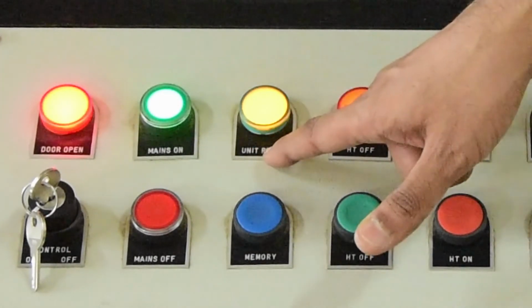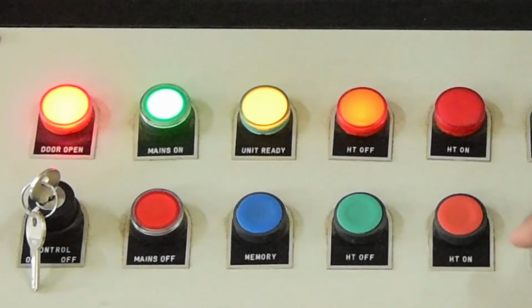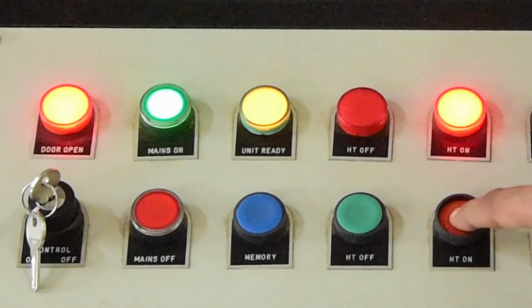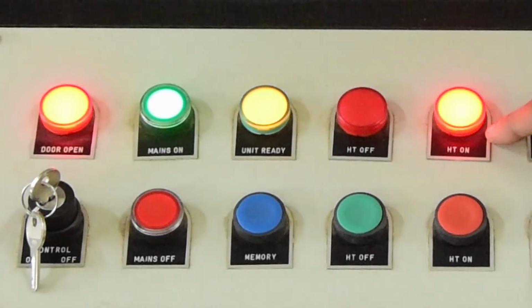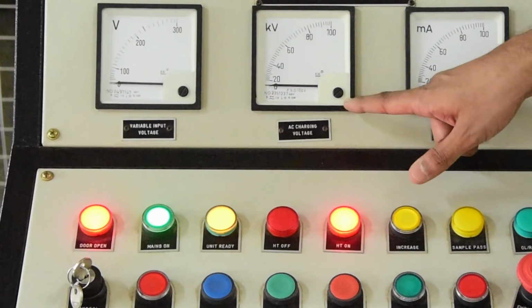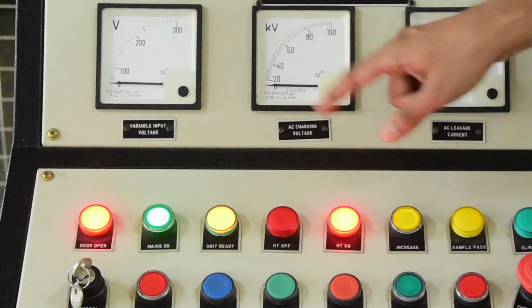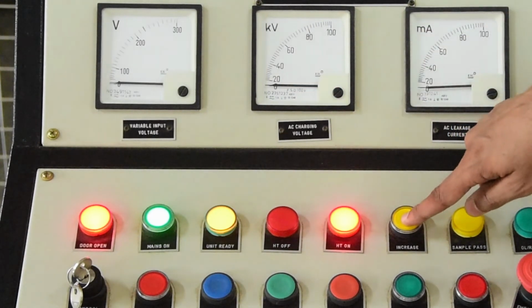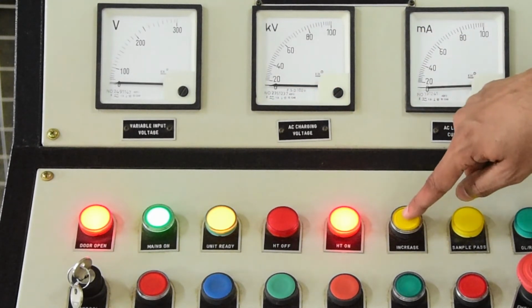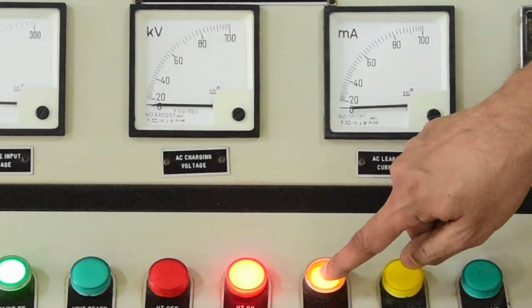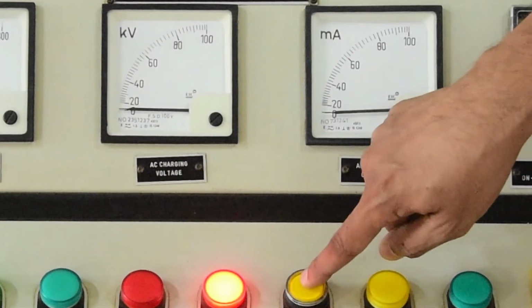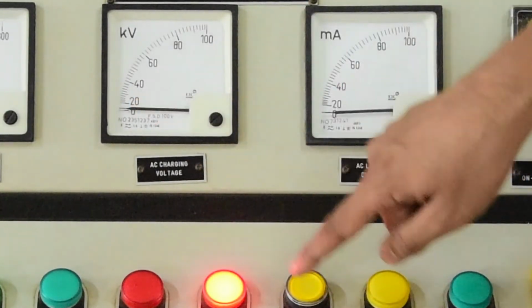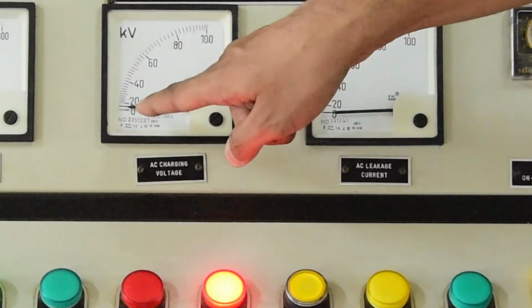It shows the unit is ready, so we can now put the HT on switch. When we place HT on, we want to apply the high voltage. Now let us press HT on. You can see this red indicator is now glowing. It indicates that we are ready to apply high voltage. Initially the observation shows 0 voltage being applied. We have to press the increase voltage switch so that the voltage tends to rise. As I press this increase switch, the voltage increases.